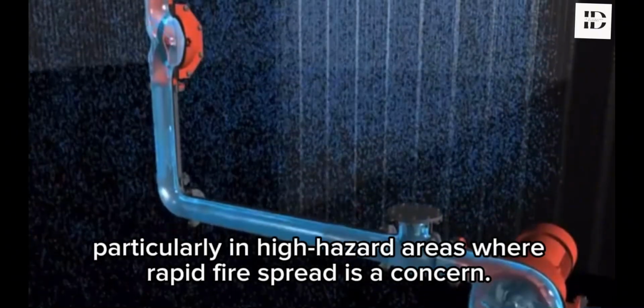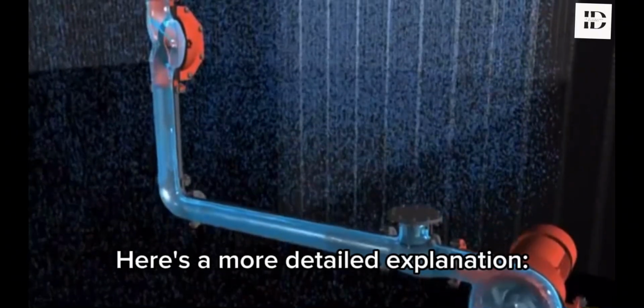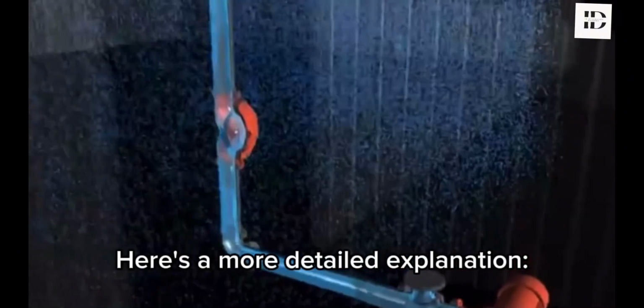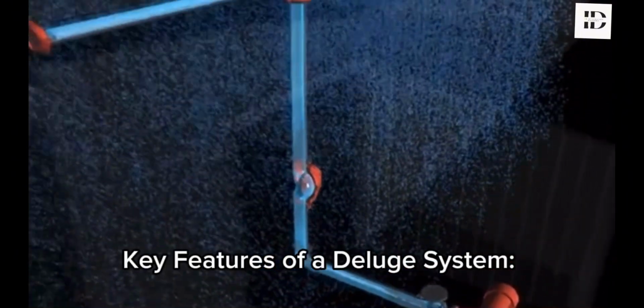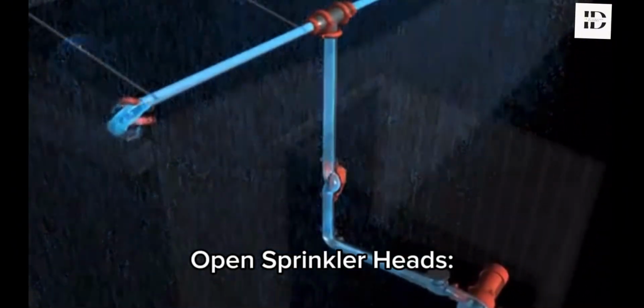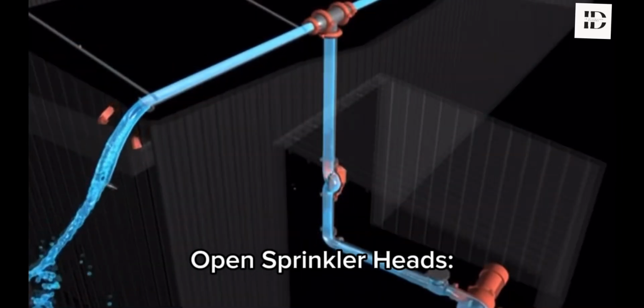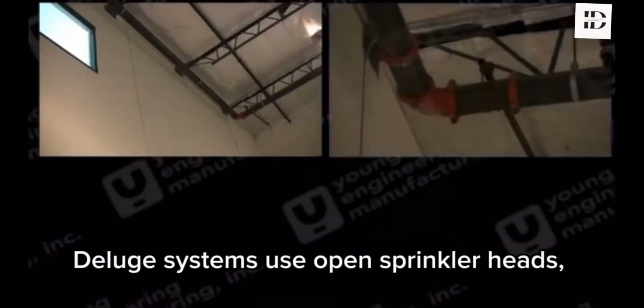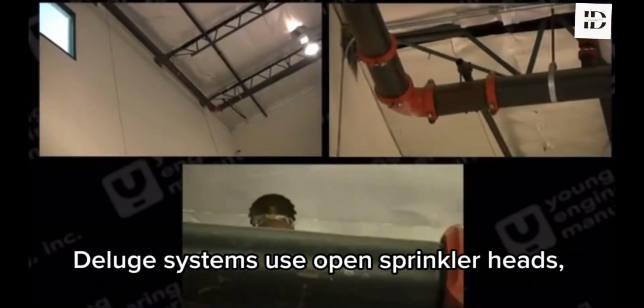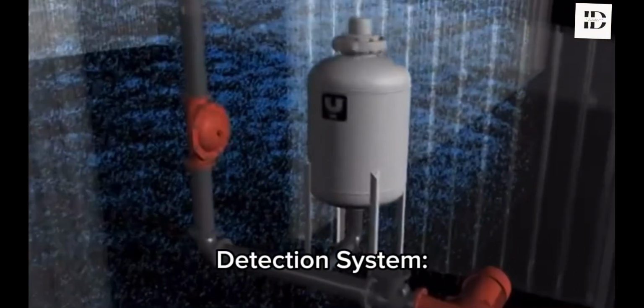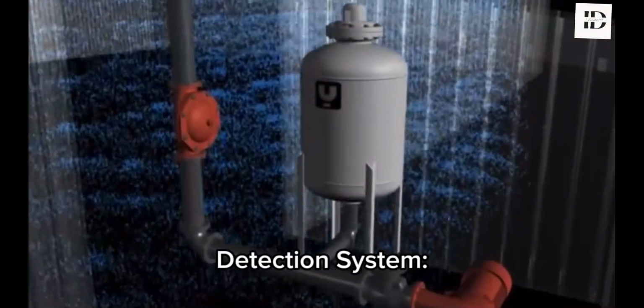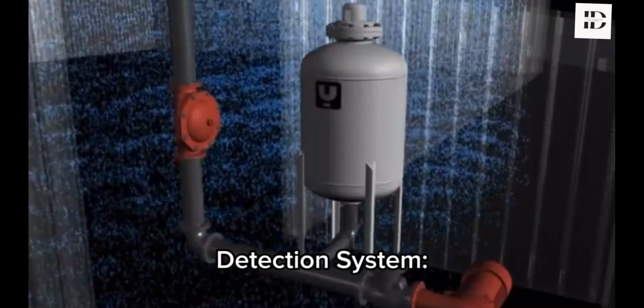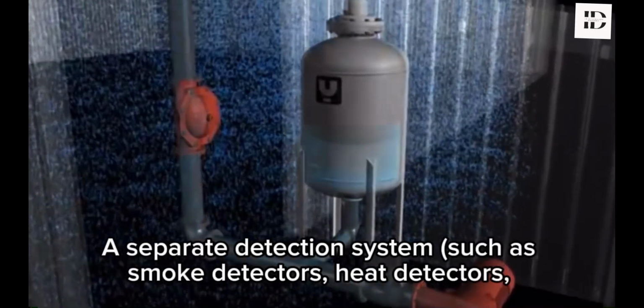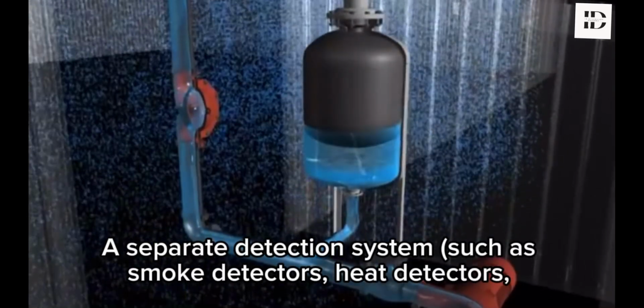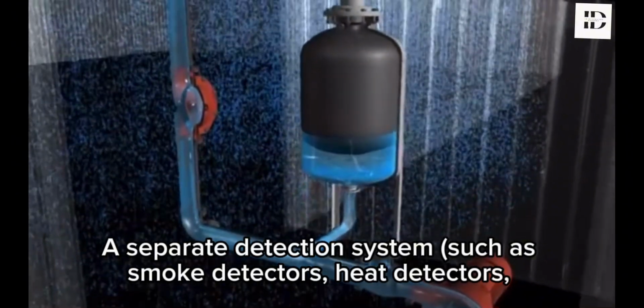Here's a more detailed explanation. Key features of a deluge system. Open sprinkler heads. Deluge systems use open sprinkler heads, meaning the nozzles are not sealed and do not require heat to activate. Detection system. A separate detection system such as smoke detectors, heat detectors, or flame detectors is used to identify a fire and trigger the deluge valve.